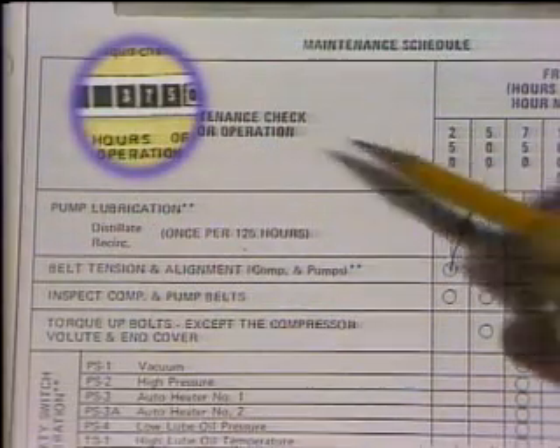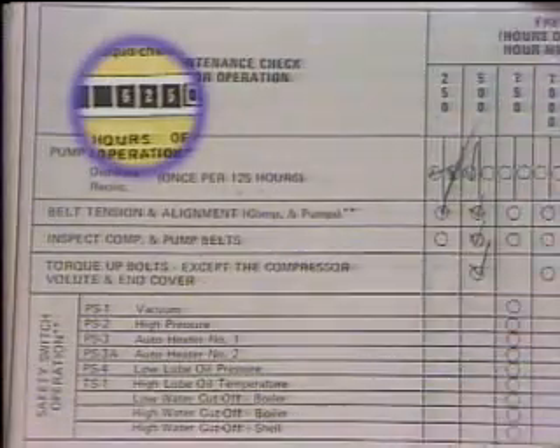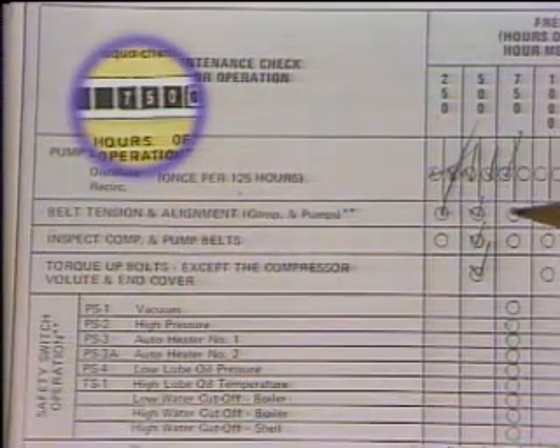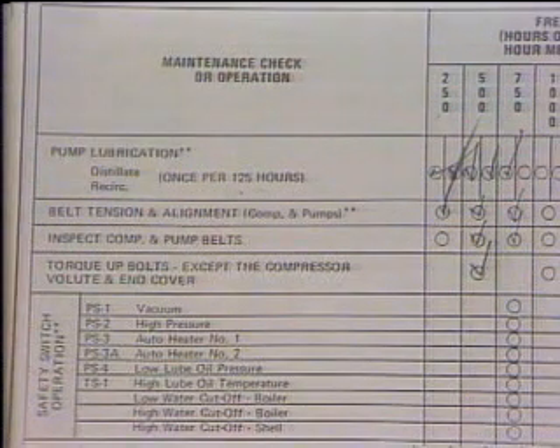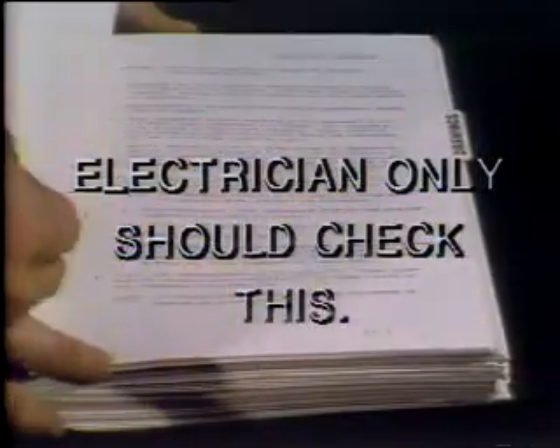When the hour meter reads 375 hours, all you need to do is lubricate the pumps again. But at 500 hours, you'll need to do all of this, plus check the torque on all of the bolts, except for the ones on the volute and end covers of the compressor. Again, at 625 hours, a pump lubrication is called for. And at 750 hours, you'll need to check these items, plus the safety switch operation, just to make sure that they're working right. Have the electrician do this. You'll find a detailed procedure in your operations manual.